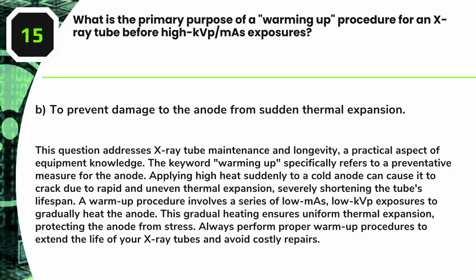A warm-up procedure involves a series of low mAs, low kVp exposures to gradually heat the anode. This gradual heating ensures uniform thermal expansion, protecting the anode from stress. Always perform proper warm-up procedures to extend the life of your X-ray tubes and avoid costly repairs.